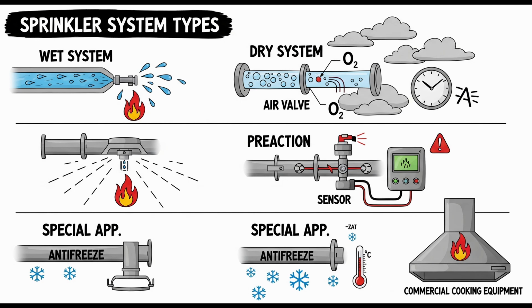Manually controlled open sprinklers, like deluge systems but manually operated, are only allowed if there's constant supervision present 24/7. You can't rely on someone hoping to be there to manually open the valve unless someone is always there and trained. So usually automatic activation. Usually, yes. The sprinklers themselves can be standard automatic, fusible link or bulb, or they can be open nozzles activated by a separate fire detection system. If automatic sprinklers are used and located in areas subject to freezing temperatures, they must be protected appropriately using a dry pipe setup, an antifreeze solution, or by being listed dry barrel type sprinklers connected back to a heated wet pipe supply. That reinforces the theme. Freezing protection is needed wherever water-filled components are exposed to cold.